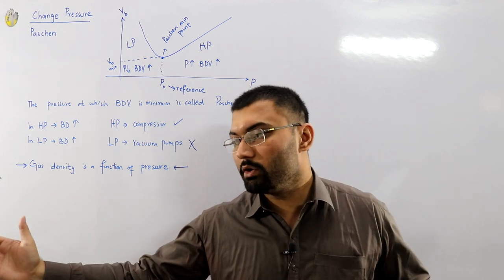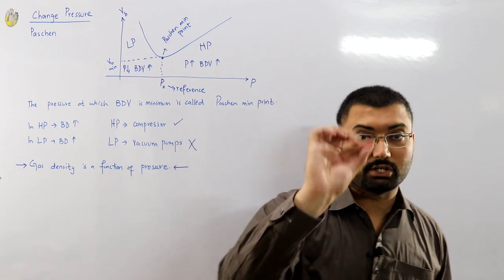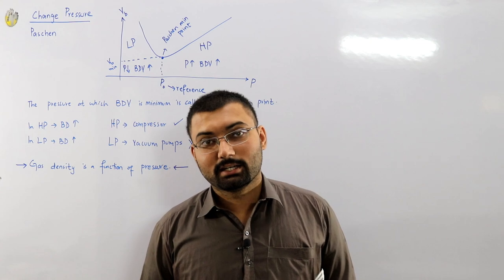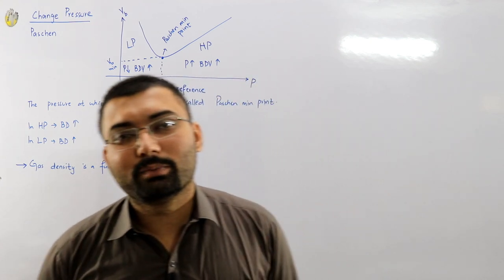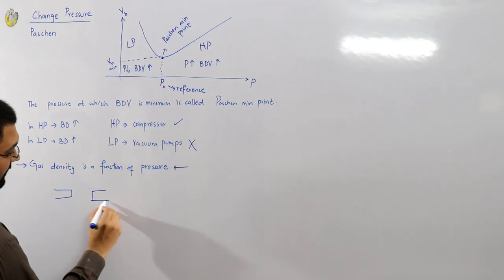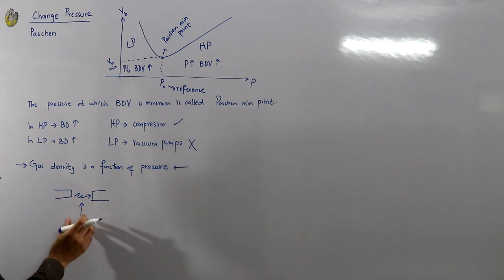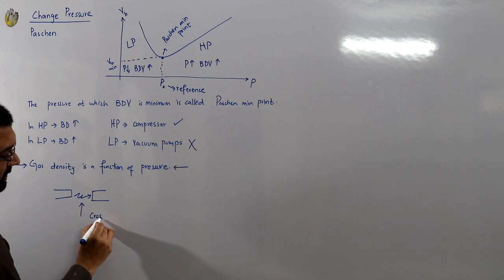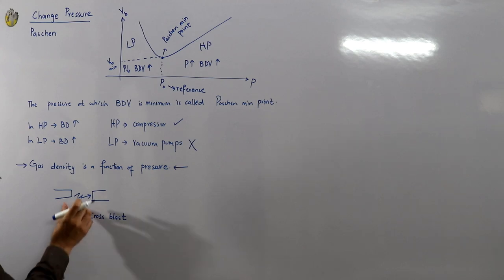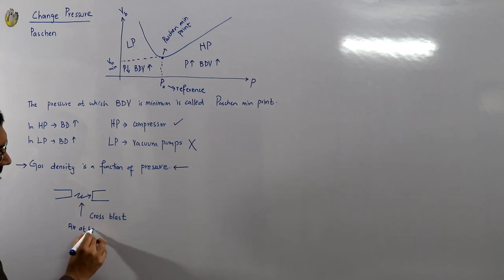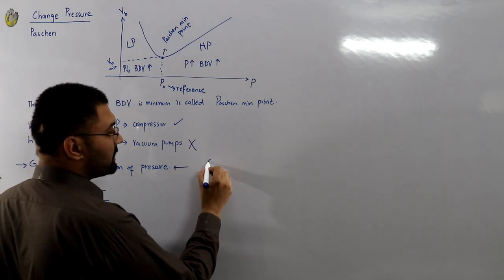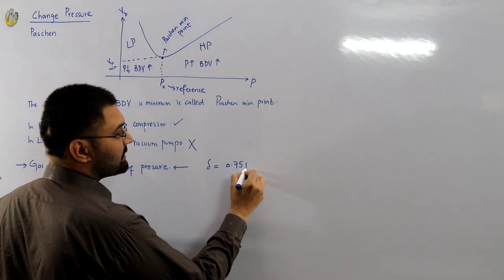When the contacts are moved to a certain distance the arc finishes, but we don't know when that will happen. So why not use air? Air is used at high pressure to blow off the arc. As soon as the contacts of the circuit breaker open and an arc forms between them, you give it air at high pressure in the form of a cross blast, and this extinguishes the arc.